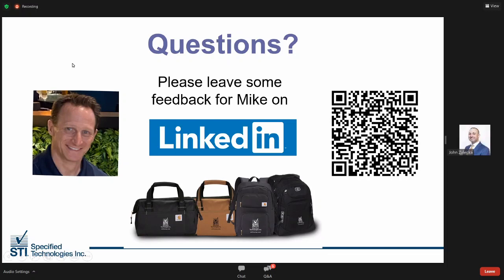All right, Christina, you want to grab that next one? Sure. Can you discuss the custom mullion fire stopping a bit more? The mullion plug? I'm assuming so, yes. Okay, I thought I heard mole. Yeah, so that would be something like when you had that design at the stack joint where there's an opening there. So there's an area where smoke and flames and sound can actually transmit through. So what we do way ahead of time is communicate and help design with the glazer the actual size of their mullions, and we'll custom cut our mullion plug to fit inside the mullions, whether it's a vertical application or a horizontal application.